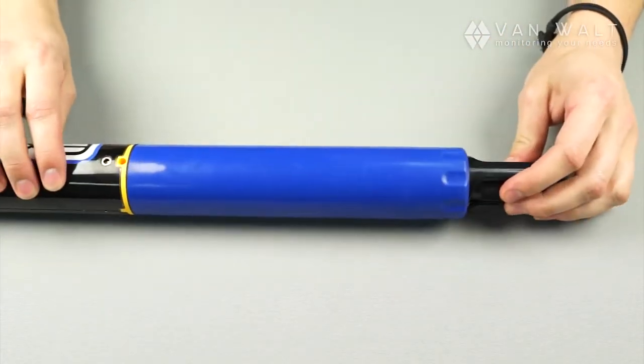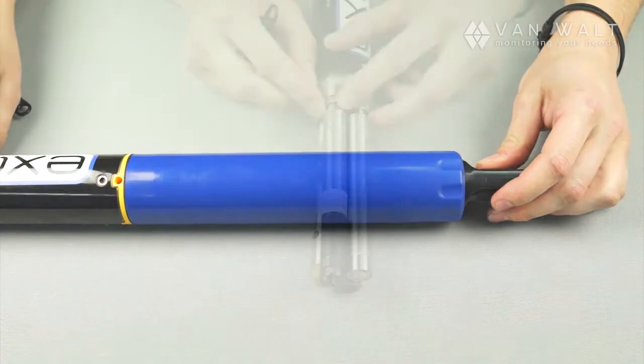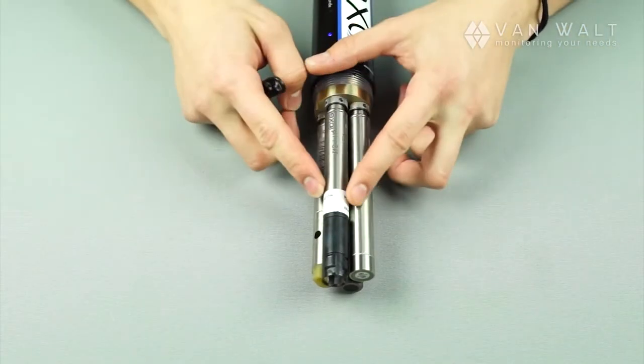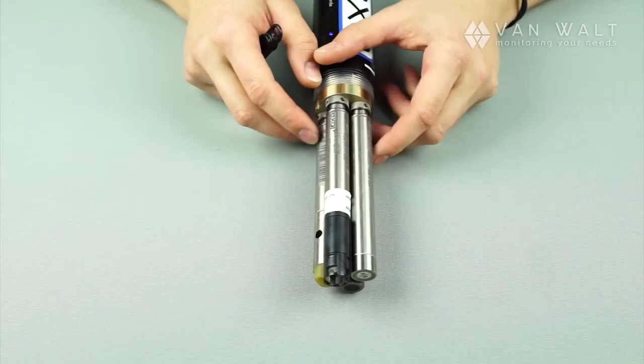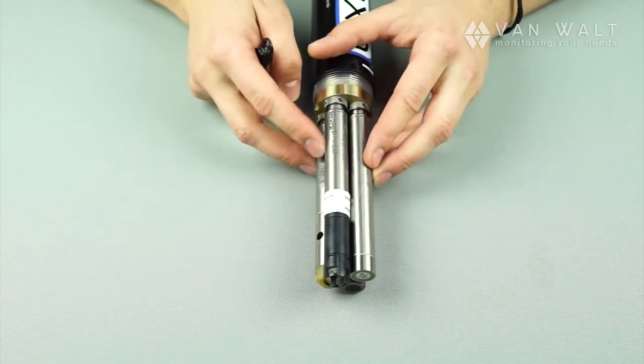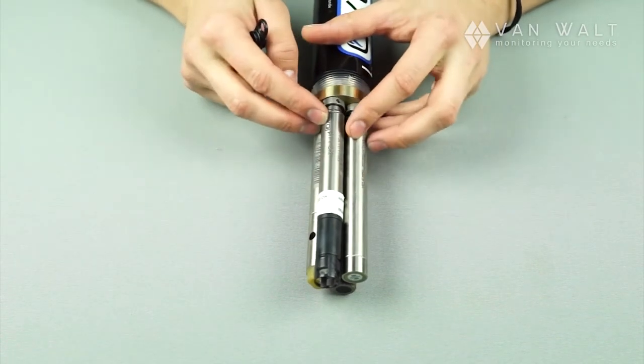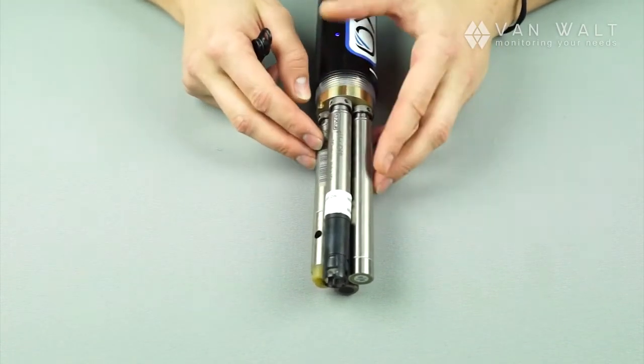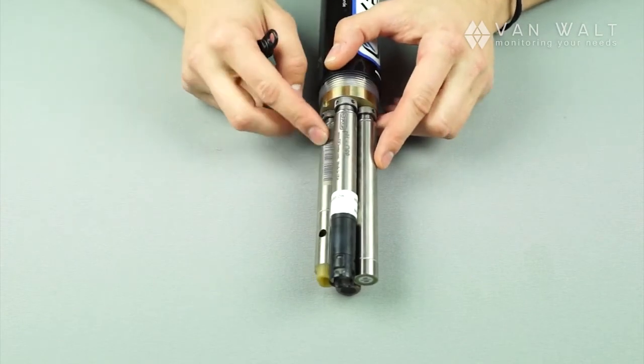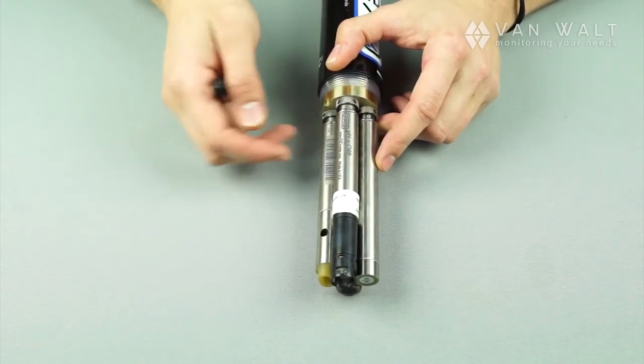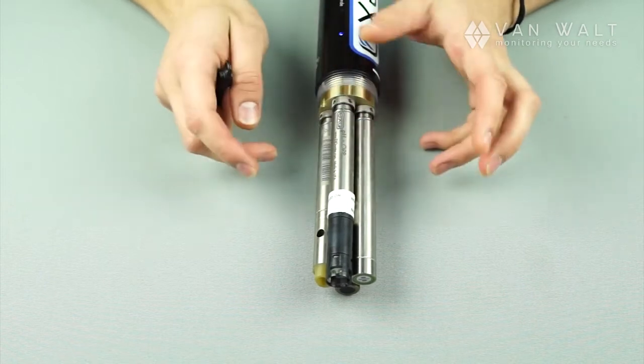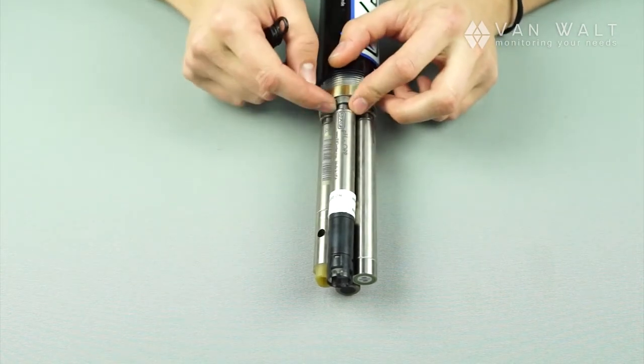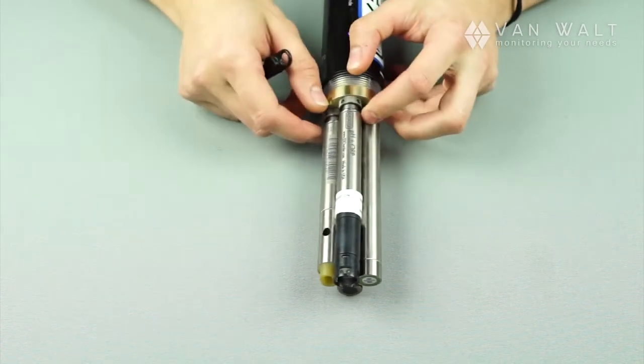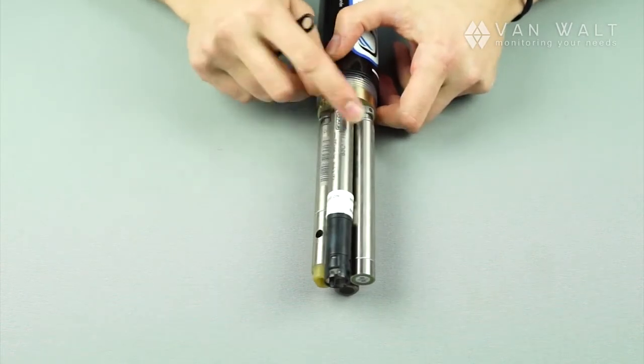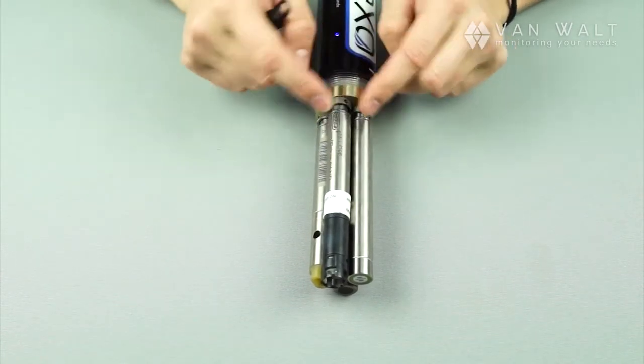The actual communication is completely wireless, and that's contained in this unit. The probes we looked at earlier, the calibration is actually stored inside the probes. So what we can do here is, if there is a problem with a probe, we could calibrate and send a probe solely to you on its own. That can be installed in your device without any calibration, and it will be reading correctly. This happens with all of the probes, again in any port.